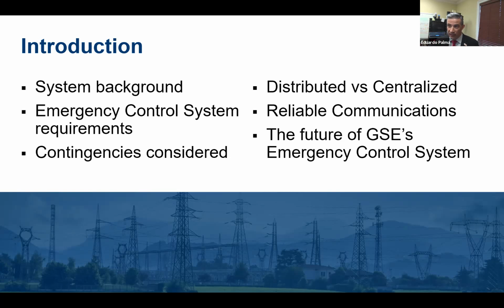We will see what contingencies were considered and how this system evolved. Evolved from distributed, which means that the control and decisions were being made by devices that were sparse, or installed in different geographical locations of the system. And then how it went to a centralized system that was complementary, that was used as a way to modernize the system in order to expand to control more points, but did not replace the distributed system. How did we get to centralized?